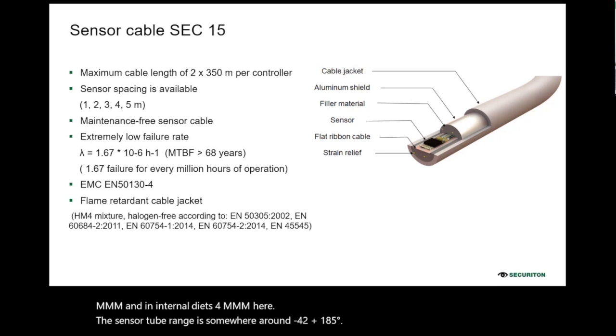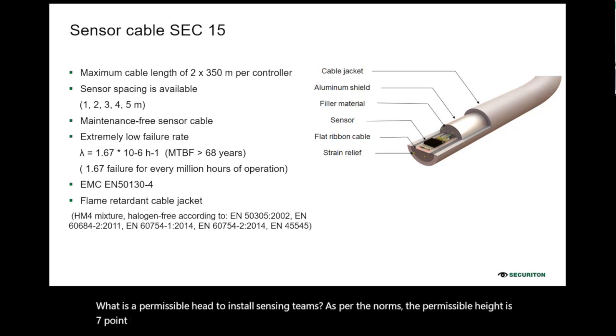What is the permissible height to install sensing tubes? As per the norms, the permissible height is 7.5 meters. And if you have a height of more than 7.5 meters, then it is always recommended to use level-wise monitoring.